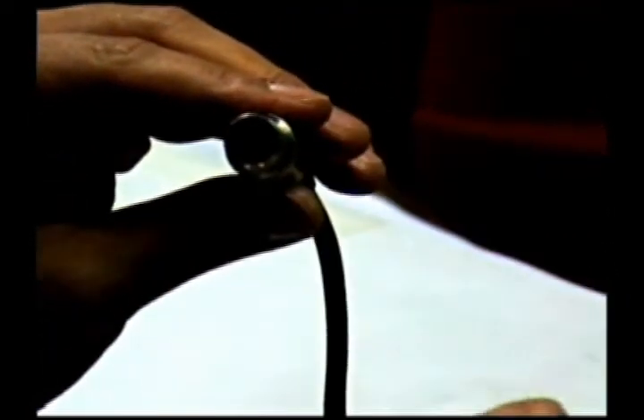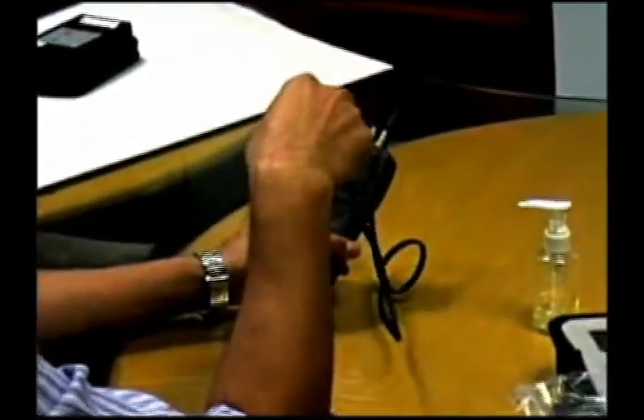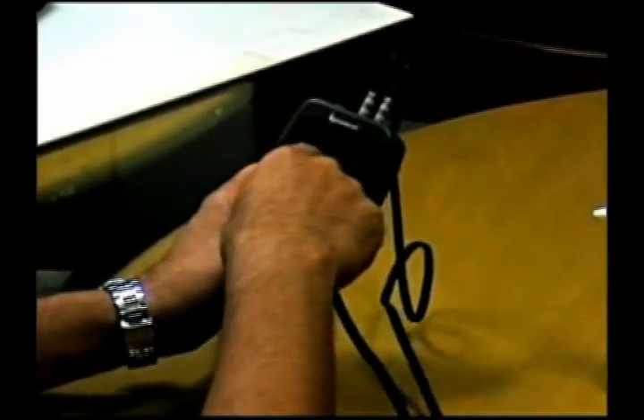Through the transmitter it sends ultrasonic pulses into the material for which the thickness has to be tested. Where the density of the material changes, the ultrasonic pulses return back, which are received by the instrument, and an accurate reading of the thickness of the material is recorded on the LCD display of the instrument.